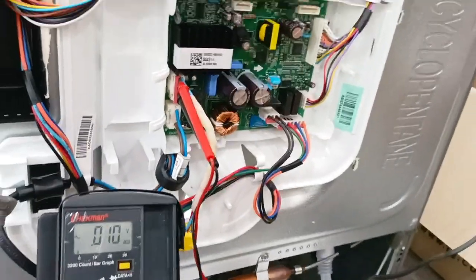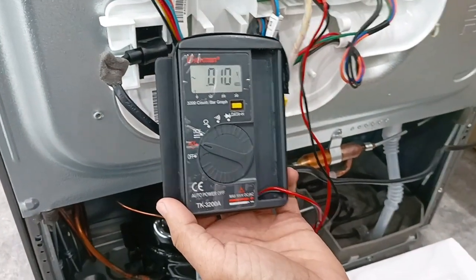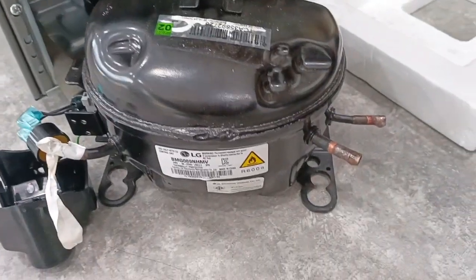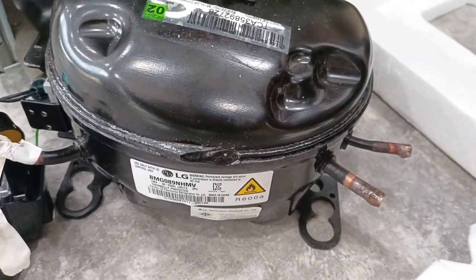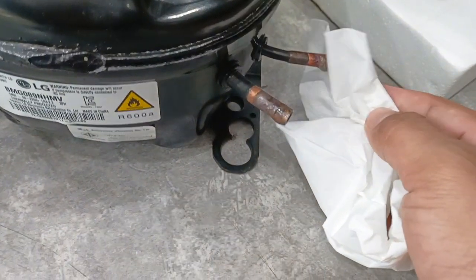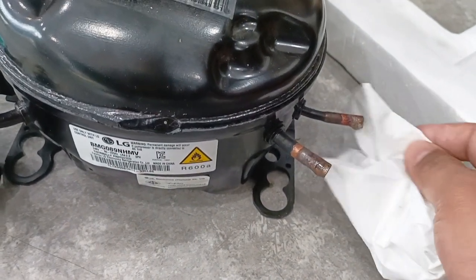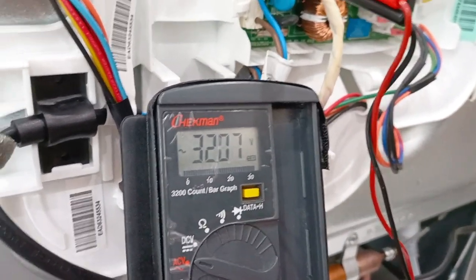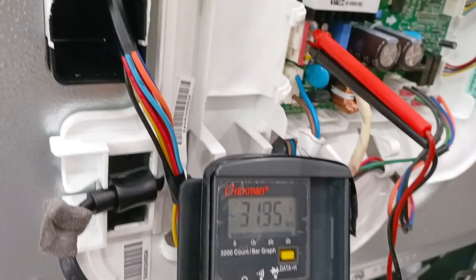Press button one and wait to see the compressor. We test from outside like this. Now the compressor is operating. The voltage supply to the compressor — this is a smart inverter with 3-phase supply to the compressor: U, V, W. You can check the supply.